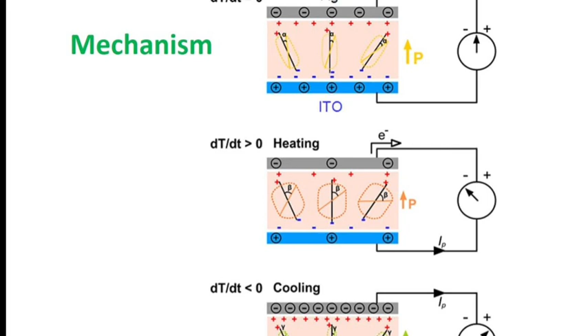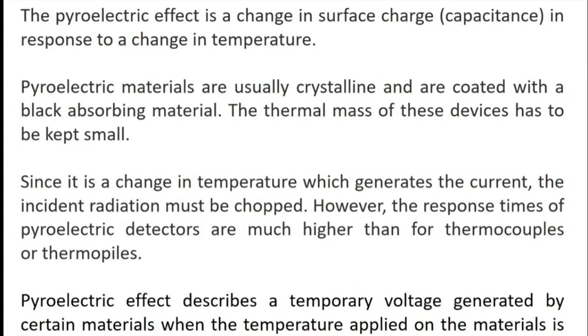The pyroelectric effect is a change in surface charge or the capacitance in response to a change in temperature. Pyroelectric materials are usually crystalline materials and are coated with a black absorbing material. The thermal mass of these devices has to be kept very small. Since it is a change in temperature which generates the current, the incident radiation must be chopped. However, the response times of pyroelectric detectors are much shorter than for thermocouples or thermopiles. Also, the pyroelectric effect describes a temporary voltage generated by certain materials when the temperature applied on the material is changed with respect to time. It is different from the thermoelectric effect, where the temperature gradient is varied in space instead of time.